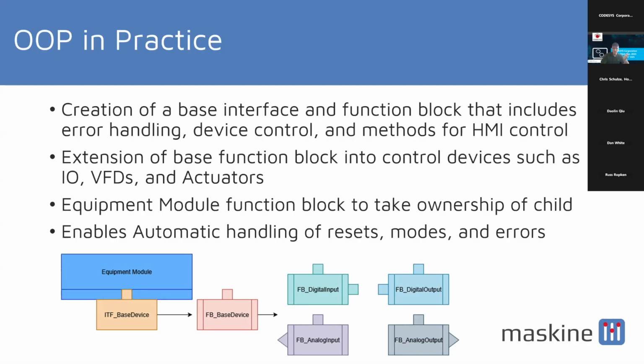A great example here is a customer that's using two different VFDs on their system, depending on what is available and the cost of it. We set it up so that the system utilizes this interface and handles everything using the ITF base device and the ITF VFD that we've defined. It allows them to easily switch between the VFD options without their sequence being impacted. The code became very clean, very modular, and independent of the hardware that's available. Especially if you have a customer who makes the same tool but changes up some hardware once in a while, this makes it very easy to streamline and develop.